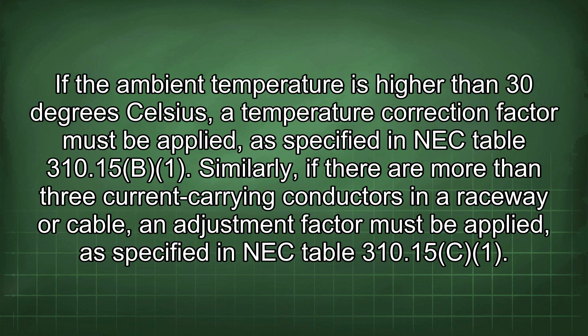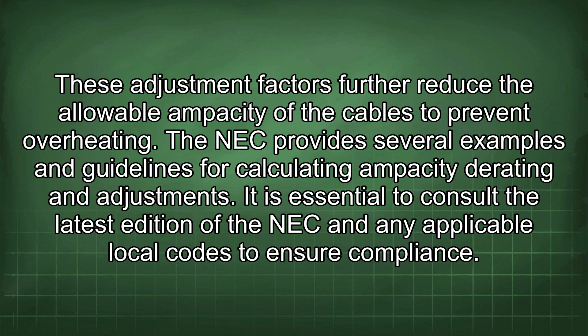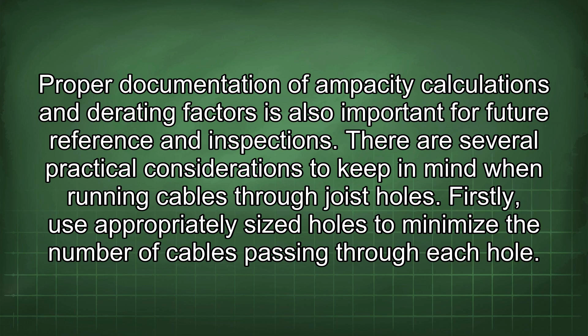The NEC provides several examples and guidelines for calculating ampacity derating and adjustments. It is essential to consult the latest edition of the NEC and any applicable local codes to ensure compliance. Proper documentation of ampacity calculations and derating factors is also important for future reference and inspections. There are several practical considerations to keep in mind when running cables through joist holes. Firstly, use appropriately sized holes to minimize the number of cables passing through each hole. This can help reduce the amount of bundling and the need for derating.